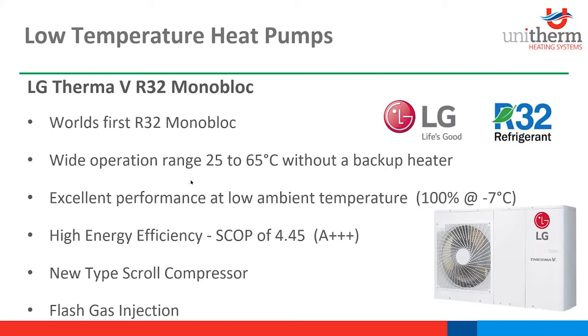So as I said there, running at lower temperatures gives minimal input with higher COP values. So how are we getting up to that 65 degrees? Well, there's a new type scroll compressor in this LG Therma V, and it varies running frequency with precise control. And the lower the flow temperature required, the lower the frequency and the lower the bills. So still though, how do we get that enthalpy to get us up to this 65 degrees, whereas a normal split heat pump will only get us up to 52, 53, maybe 55.